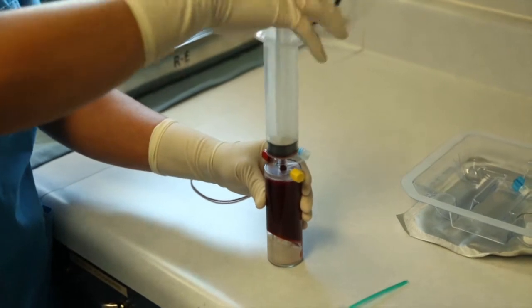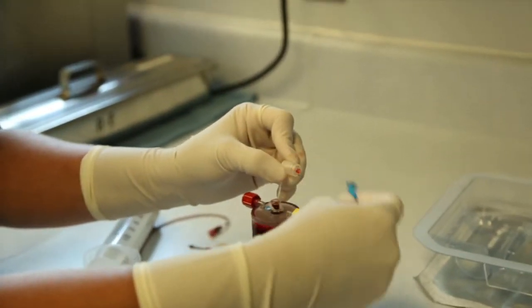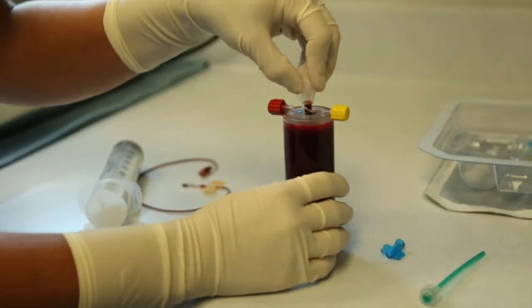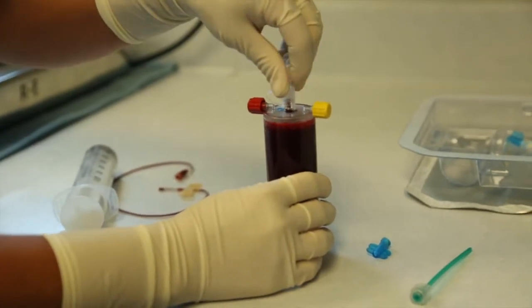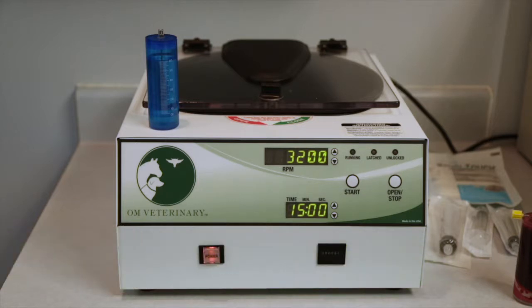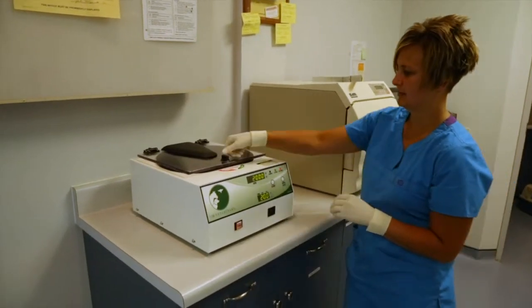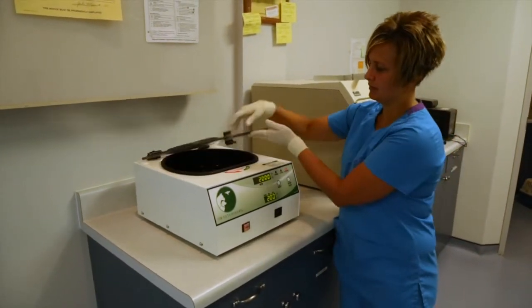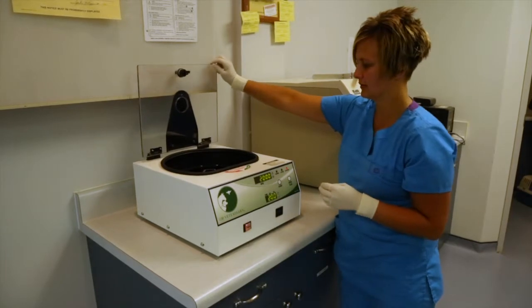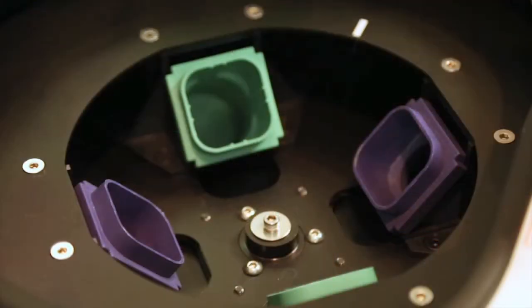After loading blood into the device, remove the blue insert by unscrewing from the center tethered cap, then secure the tethered cap to the center port. At the time of the first centrifuge spin, ensure the centrifuge is on a secure and flat surface, plugged in, and the power on. Press the open button. While gently pushing down, twist the latch on the lid counterclockwise to open. It is always good to check to make sure nothing is in the centrifuge beyond the buckets. Nothing should be kept or stored in the centrifuge when transporting.